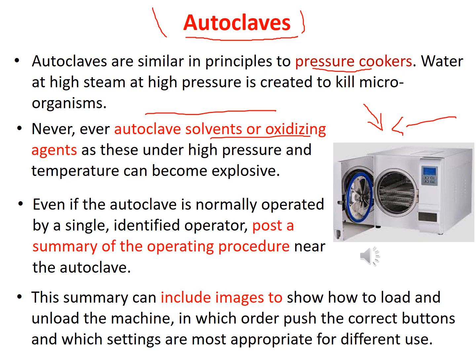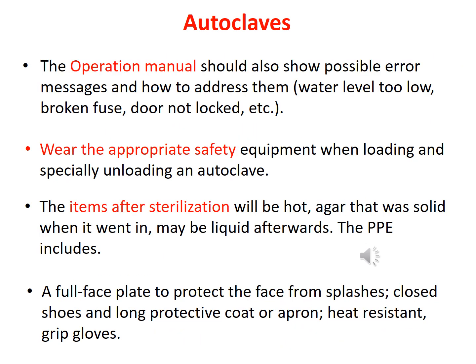Even if you're using a normal autoclave, each autoclave has particular operating procedures. In most labs the operating procedures are already posted, and they include images showing the loading and unloading of the accessories inside the autoclave. Then of course you just follow the steps, and there are certain water levels. You need to check everything mentioned in the operation manual. The manual also lists possible error messages. If there is an error, you can double check and confirm with the operation manual. Sometimes it says the water level is very low, or a fuse is broken, or the door is not locked. Follow those instructions and you can fix it very easily.